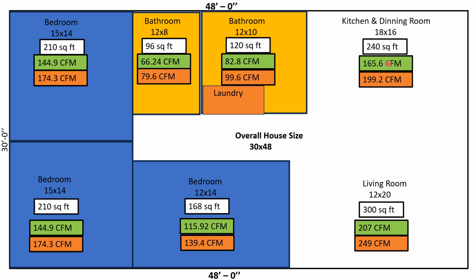This one here in the kitchen, you're talking about 30 CFMs. This one in the living room, you're talking about almost 38 CFMs. So you start adding all these up and you start seeing, hey, I have the opportunity of having a higher heat load. Let's say we've got higher ceilings in this area, or French doors or sliding glass doors going out to a back porch, and this is eastern, the sun sets in the west, so I have evening sun coming in on the back side of this kitchen beating down, so I'm going to have more of a heat load in the evening time. So those are things you've got to keep in consideration.